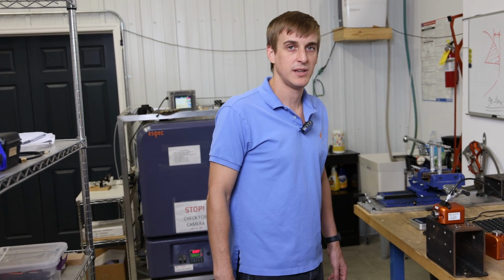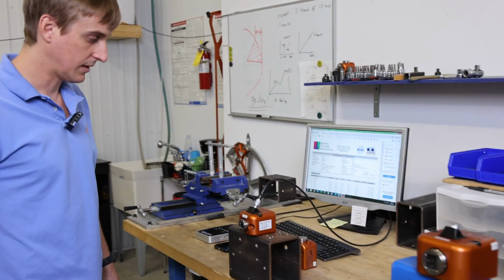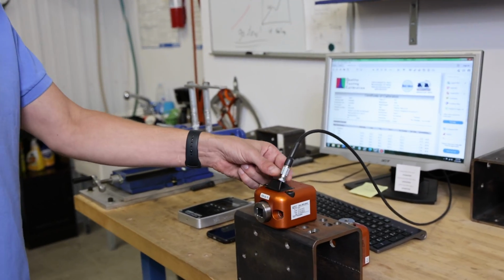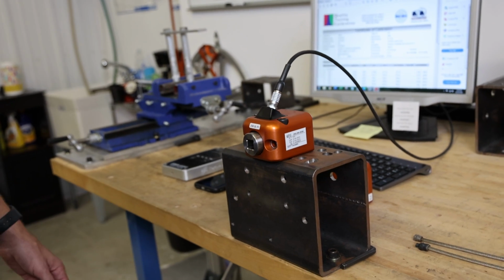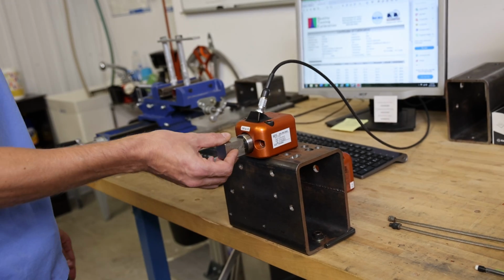In this video, we will be demonstrating how to calibrate a torque analyzer. To do this, we will be using a torque arm and our calibrated weight set.